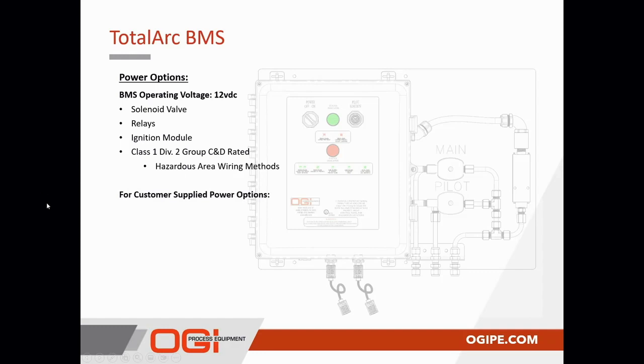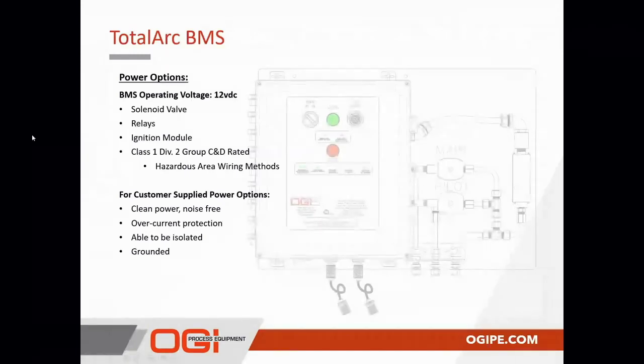When a customer is supplying power to the BMS, the power must be clean, free of noise. It must be provided with an overcurrent protection device, whether it's a fuse or a circuit breaker. The power must be able to be isolated, so whether it's a disconnect or a switch, or a circuit breaker, something where power can be positively removed from the BMS system. And finally, it must be well grounded. The principle of operation is primarily based on sensing flame relative to a ground potential. So if we have poor grounds, any BMS system like ours would potentially have issues.